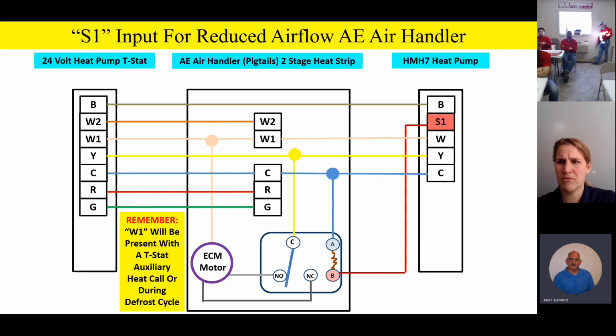That's a good question. So if the unit's at a reduced capacity and we happen to get an auxiliary heat call, it'll just drive the indoor fan motor to 100% airflow. But if the outdoor unit goes into defrost, it'll put itself into 100% capacity, because when it goes into defrost, it drives it to 100% capacity outside. When it does that itself, it'll also generate a W output from the outdoor unit to bring the heat strips on inside, which in turn will bring the indoor blower to 100%. Does that make sense? Right.